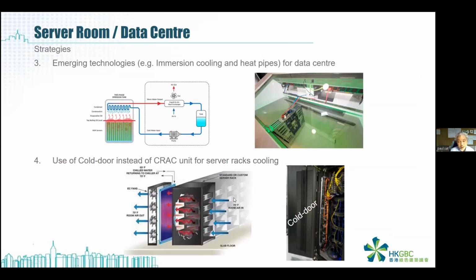Another thing that comes out is what we call the fan wall, or the cold door. Here, instead of cooling the cold aisle, you only use a cooling coil to cool the exhaust hot air. After they cool the air, they inject it directly into the space, and we use it for cooling the rack. This is what we call the cold door. It is a very latest technology, and when we use it, we can reduce the space for the data centers, so you can have many more racks in the same space.